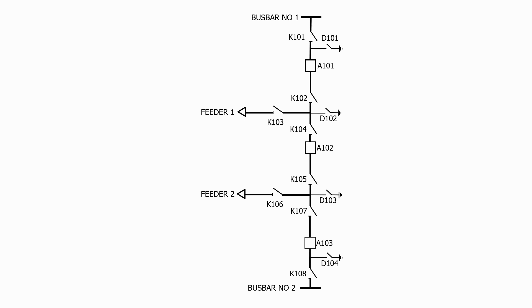Let's do a worked example. For the circuit shown, work out where the current transformers need to be to provide different protection zones to cover all of the busbars and equipment.